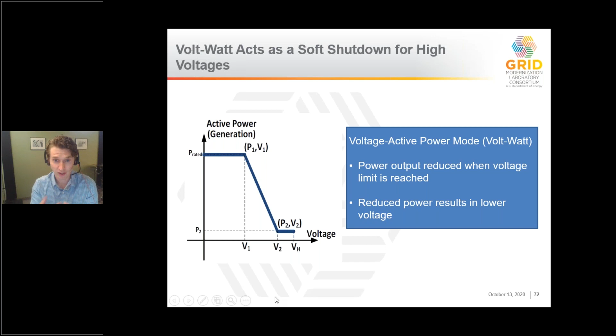The next function is this Volt-Watt. And again, we're looking at the characteristic curve where for normal voltages, we have active power on the y-axis. The DER is just going to be operating at its full rated power. But if voltage exceeds some threshold, V1 in this case, the power starts to be adjusted downward to try to help manage that voltage locally. And on the next slide, please, we're going to look at an example of this.